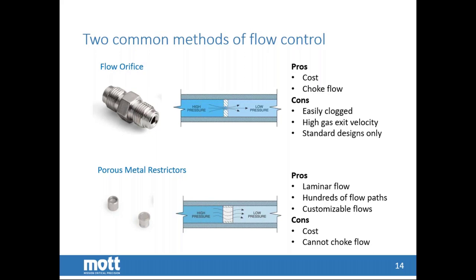The advantages of an orifice are that the cost is typically a little bit lower, and you do achieve choke flow, meaning you can only flow up to a certain amount based on the geometry. The downside is you only have one hole, so it is more likely to be clogged. You have a very high gas exit velocity, which can create turbulence in some applications, and they're very standard designs. With porous metal, there is laminar flow. You have many hundreds, if not thousands, of flow paths, so clogging becomes less of an issue. With an orifice, the accuracy is dependent on the tolerance of the hole that you drill, whereas the flow restrictors that we make are each tuned and calibrated to the specific pressure and flow conditions required in the application.